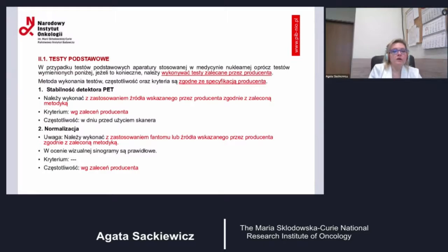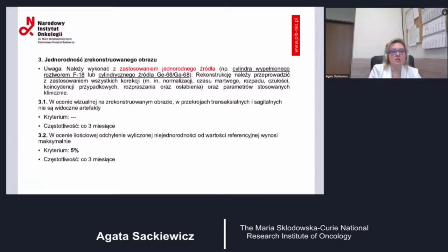These can be tests performed using different sources. Usually here we are using a visual assessment to check whether the sinograms are correct. The criterion is not defined. Frequency is according to the recommendation of the manufacturers, and this is done under daily quality control measures, and the system will enforce such tests. Homogeneity of the reconstructed image is the third test we should perform.